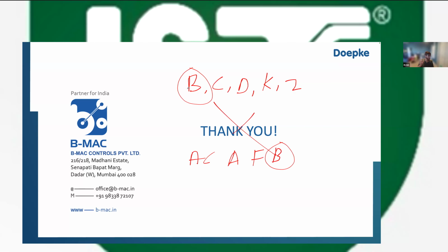They are just letters that the IEC standard has used to designate it. I know the fact that they are both B's is quite confusing for people on site, but the first thing is that you go to a specialist who understands this subject, and second, tell your guys on site that a B type MCB is very different from a B type RCD.